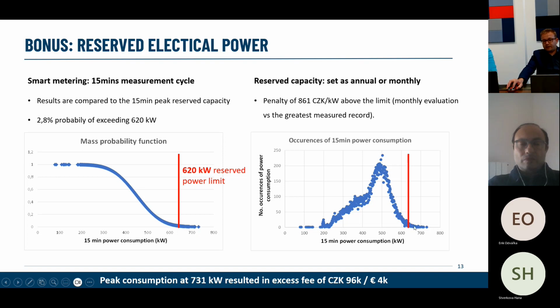So as you can see, they had occurrences where they exceeded. So I calculated a mass probability function. I analyzed the whole year span. I was provided with the raw data of the 15 minutes peak spans, and it turned out that there was a 2.8% probability of exceeding the limit. It doesn't look like a big probability, but you see there were excesses up to 730 kilowatts. So quite significantly above the reserved power. You can see that it wasn't a standard normal distribution, but a bit skewed. So I calculated the median, to mathematically interpret the probabilities correctly.